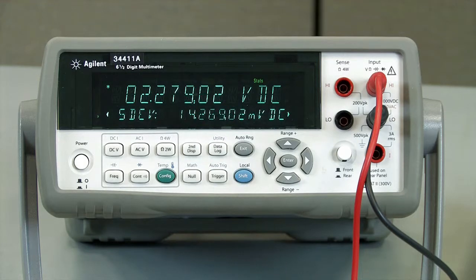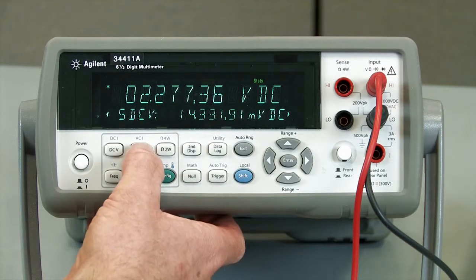And once again, we'll go ahead and look at our standard deviation. And so the standard deviation is a little bit lower than what we saw before. The integration time is almost identical to our 10 NPLC. So the reading rate is the same, but by making that slight adjustment, we can really improve the amount of noise that we're seeing on our reading.